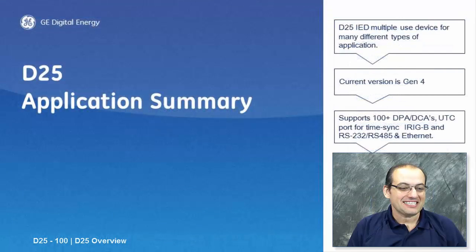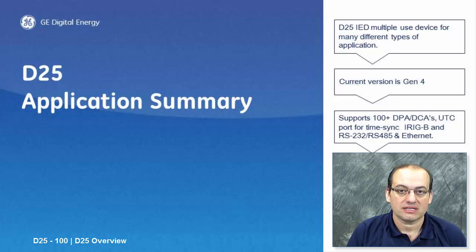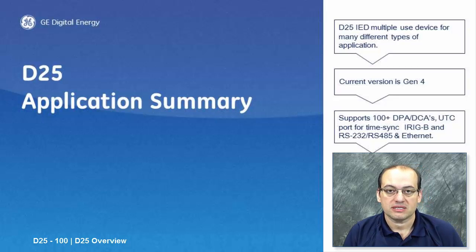The D25 also contains protection elements — for example, definite time protection and breaker failure protection schemes — which can be utilized for substation applications. In this section, we have briefly discussed seven applications of the D25 and its versatility in hardware and software. It can be utilized in many parts of your substation — at the bay, at the transformer — and not only in substations but also in industrial applications such as aluminum plants in the Gulf region.